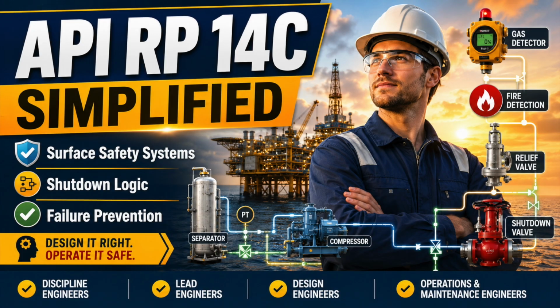The detector response must also be rational. An alarm warns people. A higher concentration may trigger automatic isolation, but shutting everything can create new hazards. Stopping ventilation may worsen accumulation. Removing power may disable critical systems. Closing a valve may create upstream overpressure. The corrective action must reduce risk, not merely create activity.